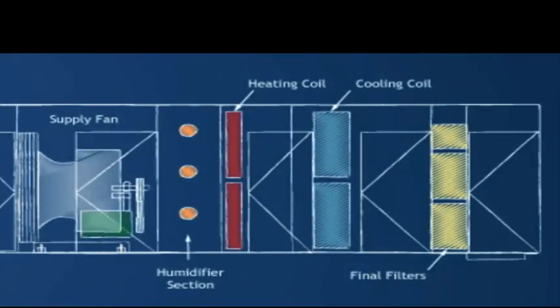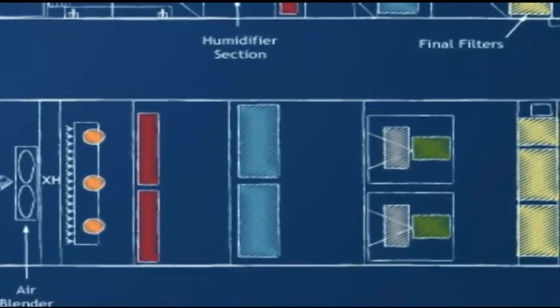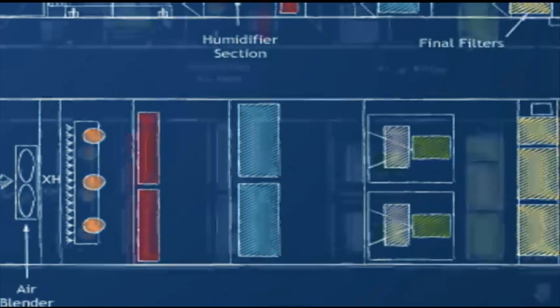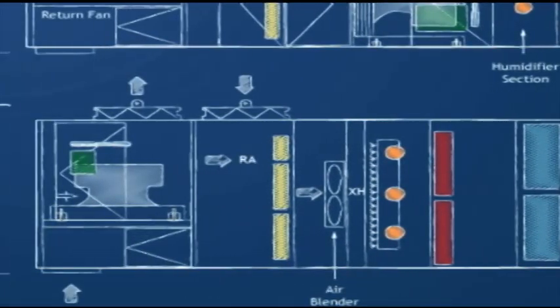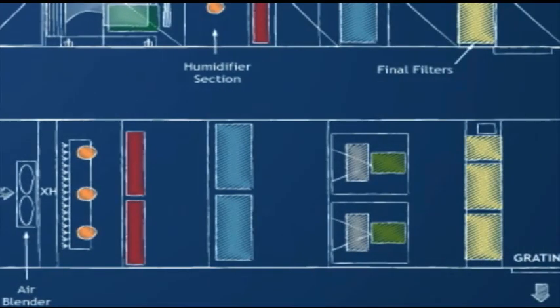This project would involve not only replacement of the fan, but also relocation of the heating and cooling coils within the air handler cabinet. Note how the two coils were to be relocated upstream in the airflow to make room for the new draw-through fan system. Smooth airflow from the fan wall array would eliminate moisture carry-through, and multiple fans would add much-needed redundancy.